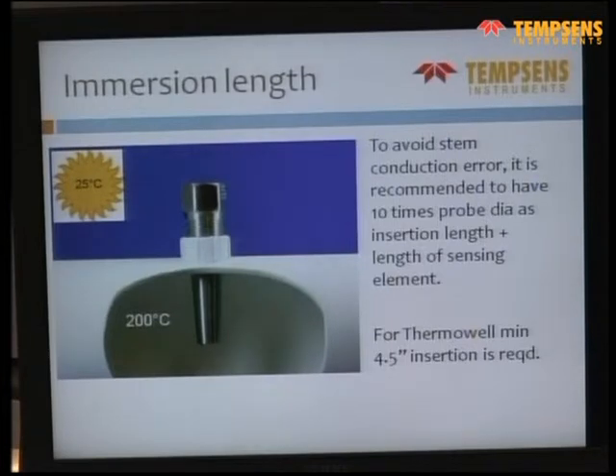Mr. Clem already discussed the immersion length, but there are just a few points I would like to add. As he already told, the insertion length for a thermowell or a sensor should be a minimum of 10 times the diameter. So we have to take care that if we do not have proper or enough insertion, there would be a large amount of error in the sensor.